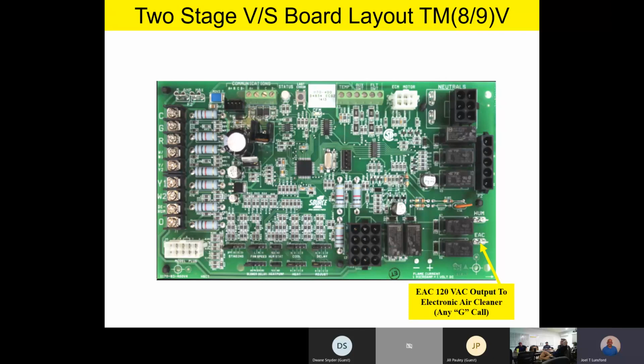air cleaner. Now this is really important. The reason I'm making a point of this, we don't want you grabbing 24 volts off the terminal strip to power up, for instance, a 24 volt air cleaner or a humidifier. That's why we give these isolated relay outputs. So if you do have a 24-volt humidifier or a 24-volt electronic air cleaner, be sure and take a step-down transformer off of these terminals here that are 120 volt, and then step it down for your accessory product, whether it be a humidifier or an electronic air cleaner. Does that make sense to everybody? Any questions or comments on that? Everybody good? We're good. Okay.